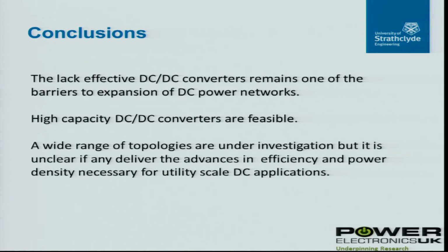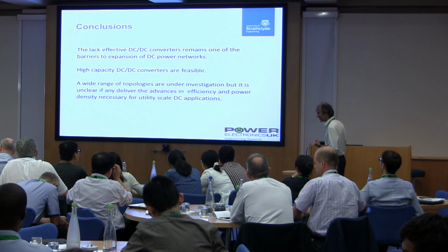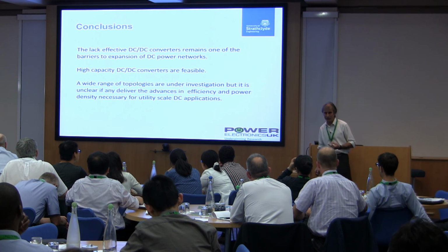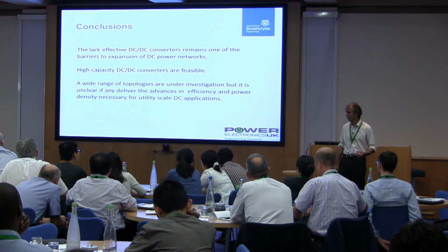So, conclusions, and I struggled to find any kind of really good conclusion. To summarize it, you could build a high-capacity, megawatt-scale DC-to-DC converter. There's no breakthrough technology in the way the Marquardt version of the MMC converter really made HVDC to AC converters much more practical. And the reason there isn't is because you need to raise the fundamental switching frequency, or fundamental power frequency, if you're really going to make any gains out of these devices.